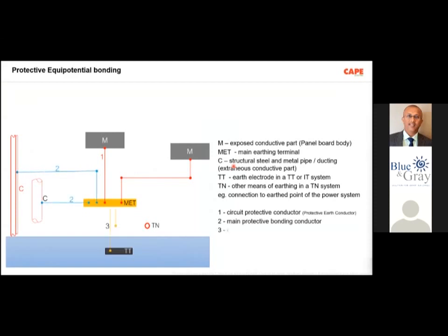I am showing a picture where you can see M stands for exposed conductive parts. What do we mean by exposed conductive parts? Class 1 equipment which is having an exposed conductive part is connected to the MET, a common bus bar. Item number C, like the metallic pole or the metallic ducting or metal pipes, these are also connected to the MET, the main earthing terminal or equipotential bonding terminal.